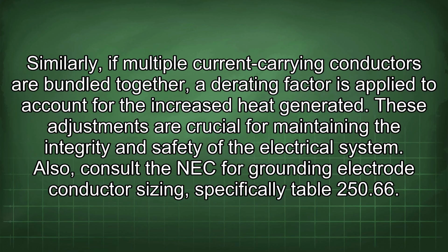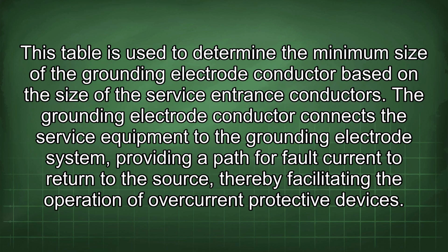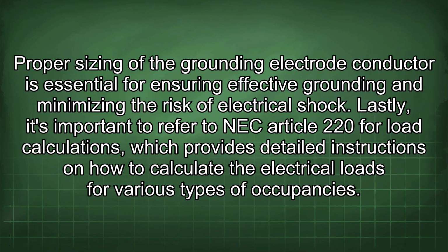Also, consult the NEC for grounding electrode conductor sizing, specifically Table 250.66. This table is used to determine the minimum size of the grounding electrode conductor based on the size of the service entrance conductors. The grounding electrode conductor connects the service equipment to the grounding electrode system, providing a path for fault current to return to the source, thereby facilitating the operation of overcurrent protective devices. Proper sizing of the grounding electrode conductor is essential for ensuring effective grounding and minimizing the risk of electrical shock.